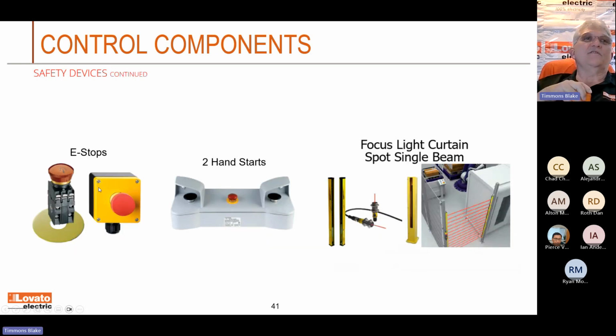Okay. There's some other safety devices, some e-stops, palm buttons. And again, these aren't just palm buttons. These are actually safety rated palm buttons. There's a standard for that. 2-hand starts. What is that all about, Mike? Well, if I reach over and put one hand on one of those black buttons and get to talking to somebody, and then I reach over and hit the other button, it won't start. It's got a little timer in there. You have to hit both of those buttons in a certain amount of time. Otherwise, somebody may take one of those buttons down, or they may wedge something in there, so they only have to hit one button.